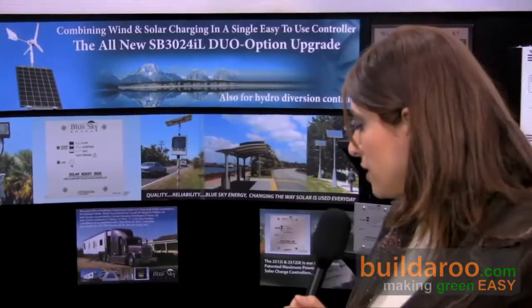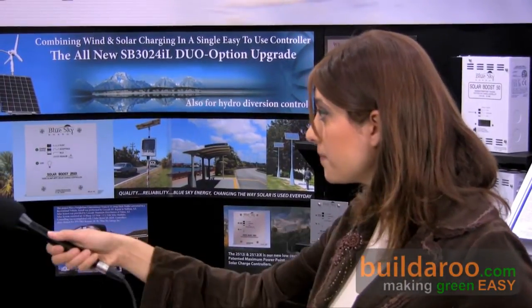One advantage is that you can use all the maximum power extracted from the solar — having the solar continue to run at maximum power even though the battery doesn't need it, and then having that power diverted to a useful purpose like heating water. It would be possible to have a separate solar controller and a separate diversion controller, as was done before the advent of this product, but the problem is you've got two different charge controllers with two different charge control systems, their own set points, their own displays, their own temperature sensor — a messy setup where the interaction between the two charge controllers is not smooth. With this implementation, there's a single charge control system directing the activities of multiple power controllers — the MPPT and the Diversion — to charge the batteries as a single coordinated machine with one temperature sensor, set points in one place, and one display.